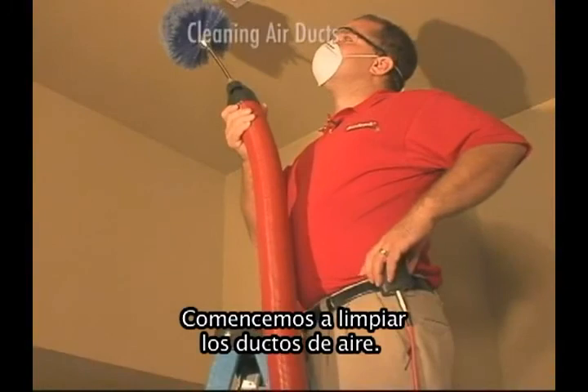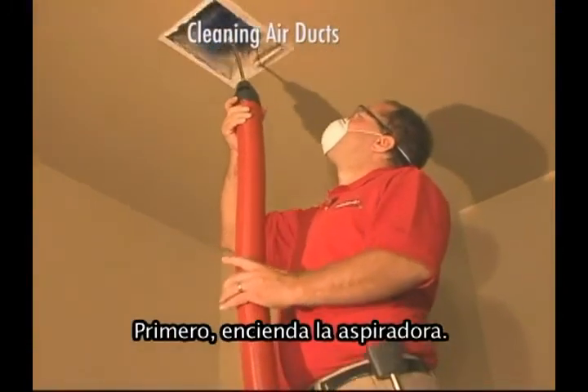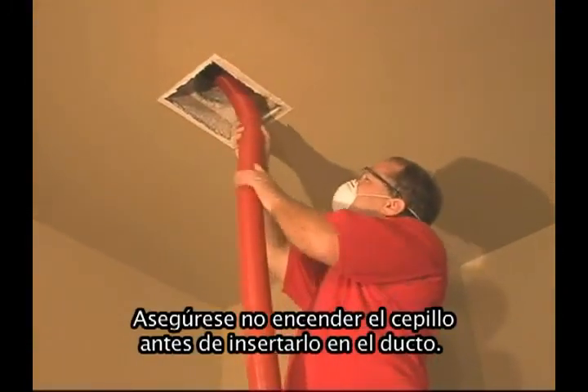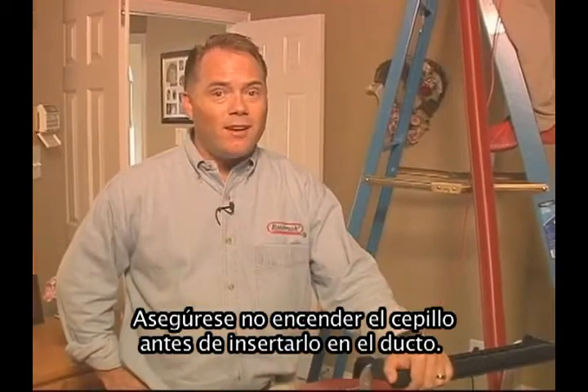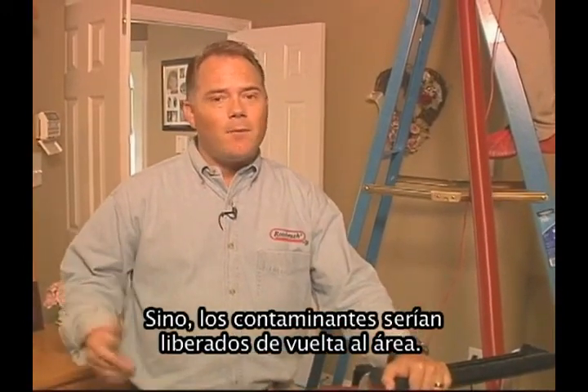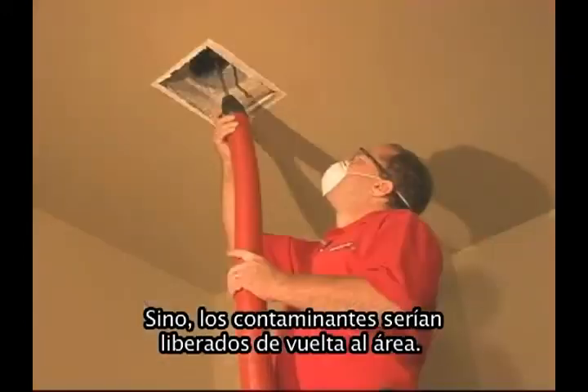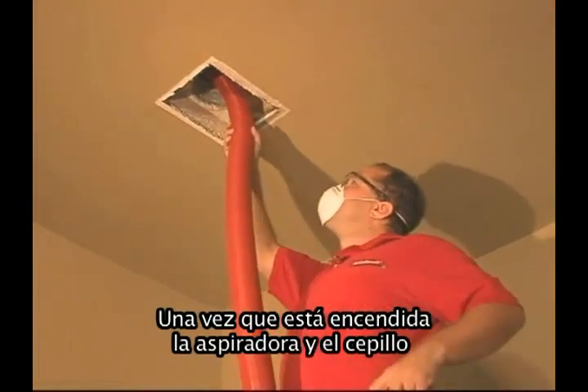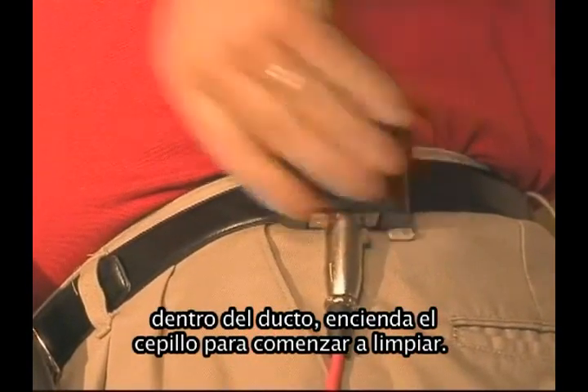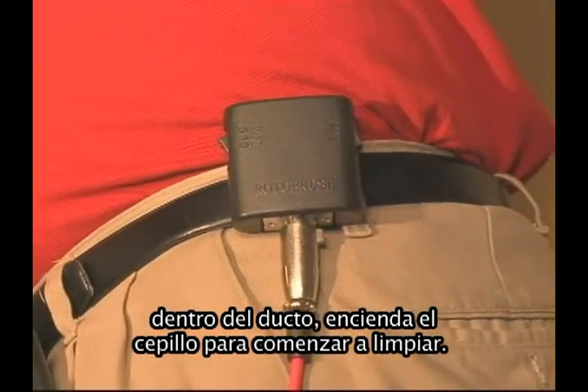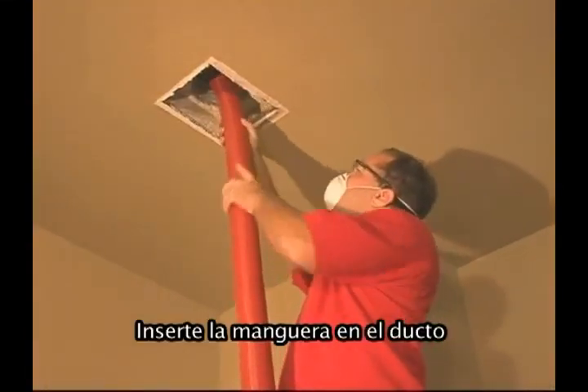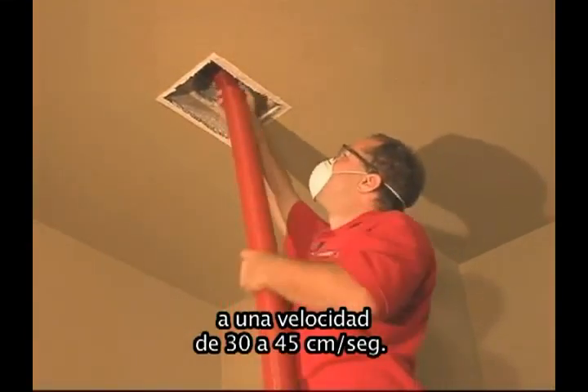Let's start cleaning air ducts. First, turn on the vacuum switch. Make sure you don't turn on the brush before you actually insert the brush into the air duct. Otherwise, contaminants could release back into the area. Once you have the vacuum on and the brush is inserted into the air duct, turn on the brush rotation and start cleaning. Insert the hose into the air duct at a rate of about 1/2 to 1 foot per second.